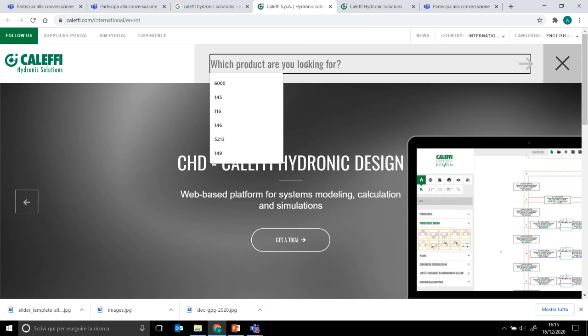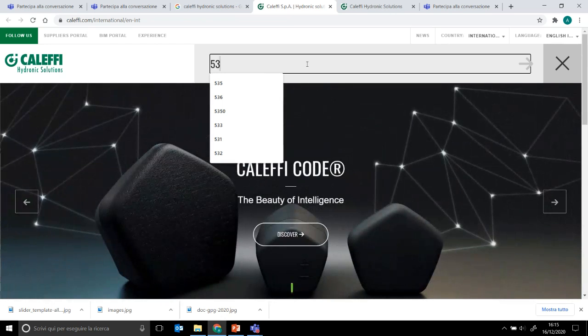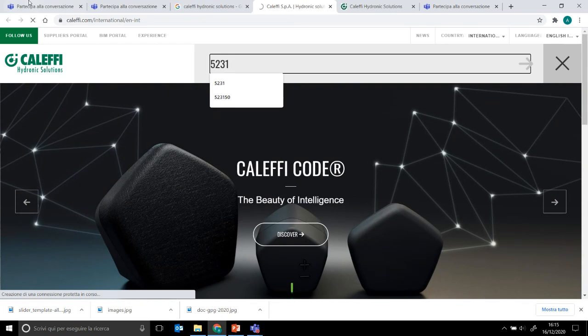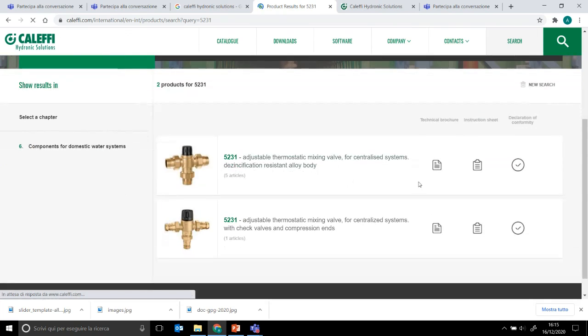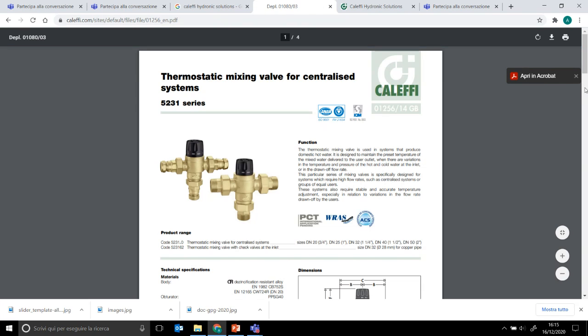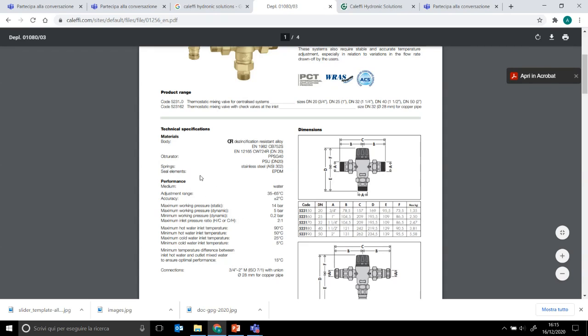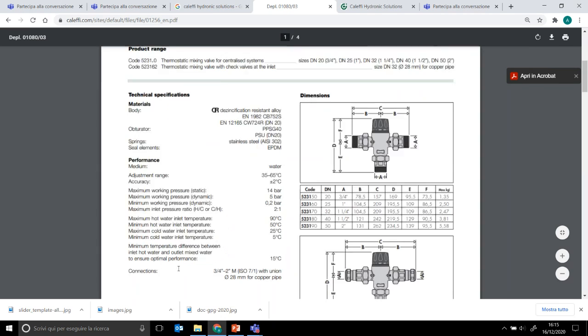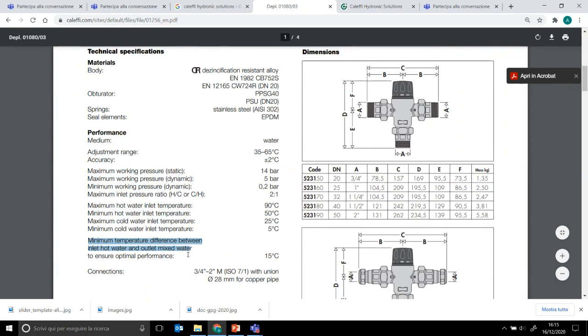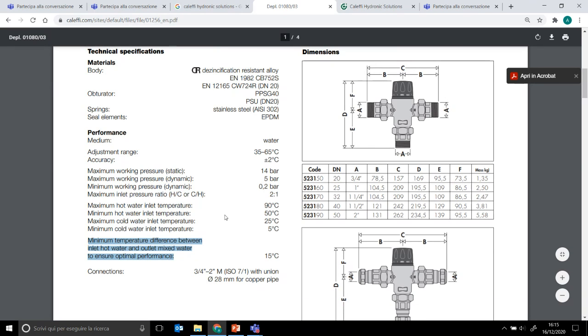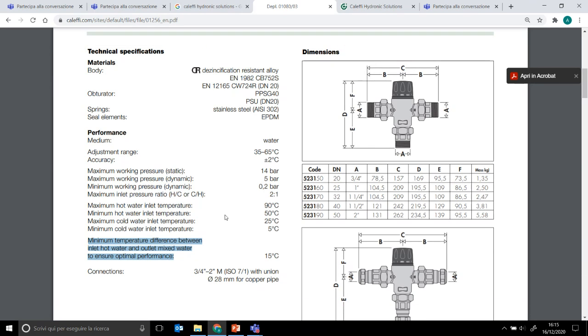For instance, let's look at the thermostatic type, the big sizes. Can you see the technical data sheet in front of you? I can, yeah. Okay, for this family, for instance, the minimum temperature between the inlet of hot water and the outlet mixed water to ensure the performances stated in the data sheet, so accuracy ±2, is 15 Celsius. Other families have a different type of sensor inside, and they have slightly different values.